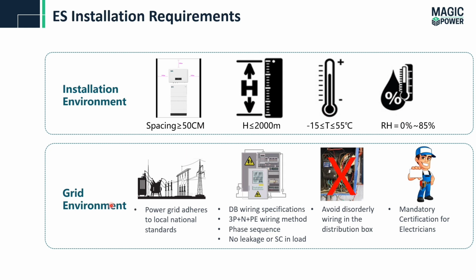If we talk about the grid environment, we should check the grid standard with the system. For the distribution box wiring, in case of single or three phase. In case of three phase, we have to check the phase sequence, and there should be no leakage or short circuit on the load side, and we avoid disorderly wiring in the distribution box. And for installation, there must be a certified and professional technician or electrician for the system installation.